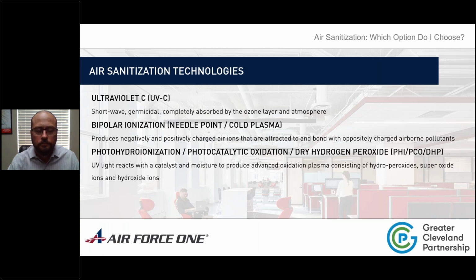So yes, people will argue that the air coming back goes through the UVC stream and gets sanitized. The problem is, to have enough ultraviolet light to sanitize air as it moves through the system at those high velocities, it would require a very large amount of electricity and an intensity that would actually self-destruct your equipment—because the ultraviolet light would destroy any caulking, anything that's not metal, and can even damage metal inside the equipment. So although it does a great job of sterilizing point-of-use surfaces, it cannot be in direct contact with people. It can damage your eyes within seconds, and it can't truly sanitize the air as it moves through, because the amount of UVC light you would need is well beyond the scope of a typical installation and equipment.